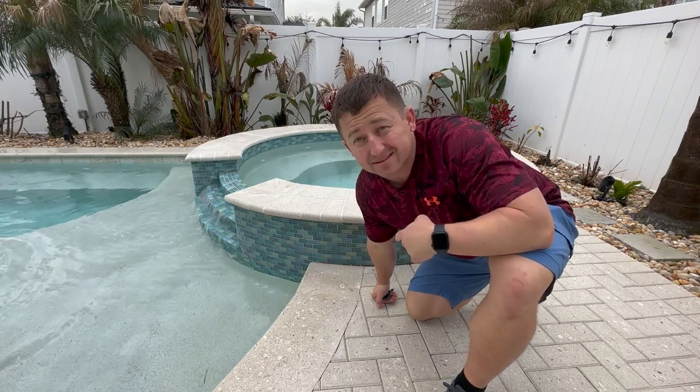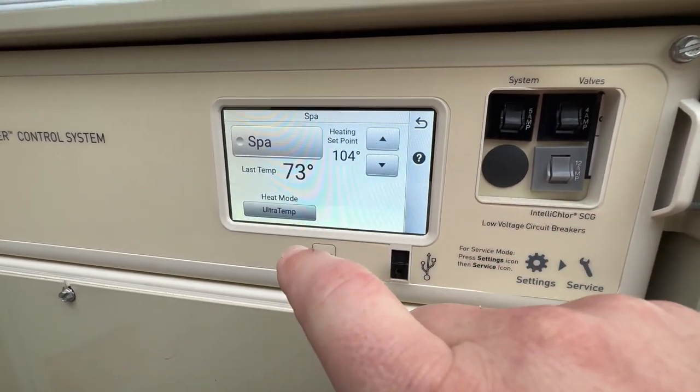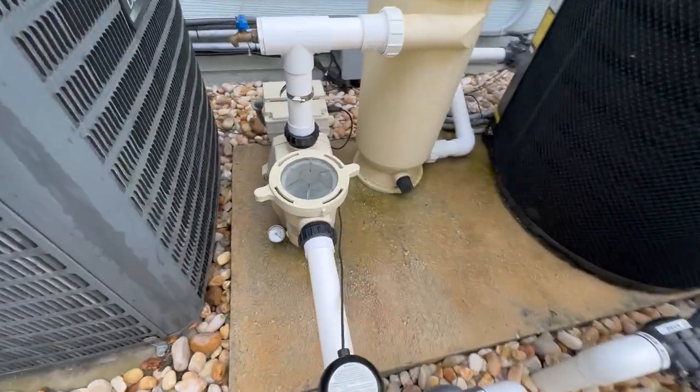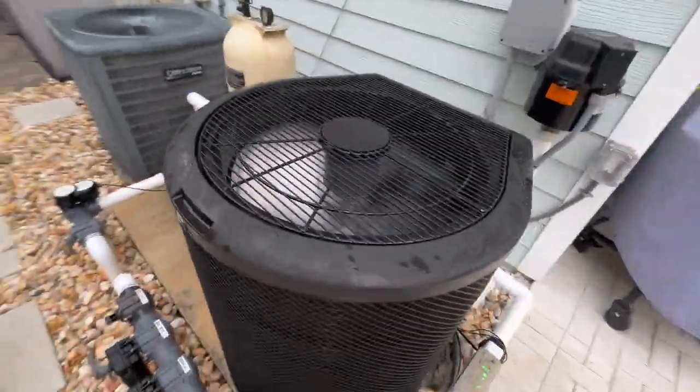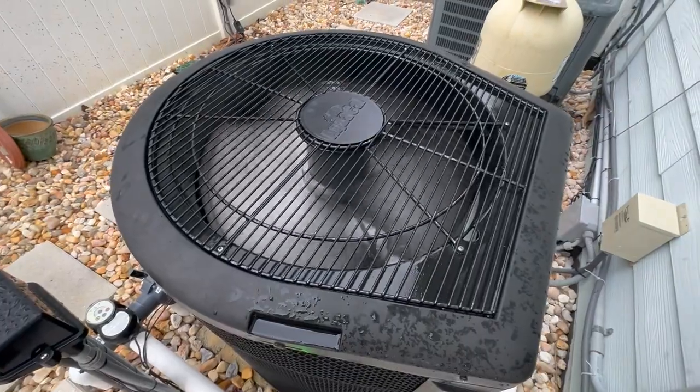We primarily use the heat pump to heat up the jacuzzi, and during the winter that's a necessity. So I figured I didn't turn the spa mode on, so let's try that now. The pump kicked to a higher gear. Let's see what happens. It's still kicked off after 30 seconds — you just saw that, right? And it goes right back to kicking back on. I'm going to see if the water coming out of the jets in the spa is getting hotter. I know it's not the number one way to check, but I'm going to keep it simple here from my diagnosis.